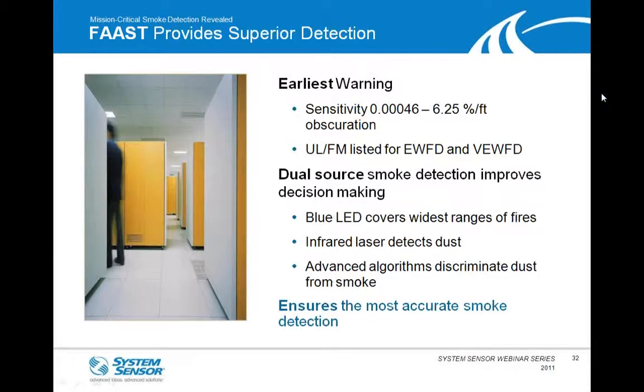So what does FAAST have to meet those needs? For one thing, it has the broadest sensitivity capabilities of any aspiration product on the market, from 0.00046 to 6.25. You might say, why does it have to be so low if all I have to get down to is 0.2? Well, remember, with air aspiration, the device has to be set significantly lower than the sampling point in order to have that effective sensitivity at the point. FAAST is also UL and FM listed for early warning as well as very early warning fire detection. So it has passed the wire burn and other tests that are laid out in the standard in order to carry this listing.